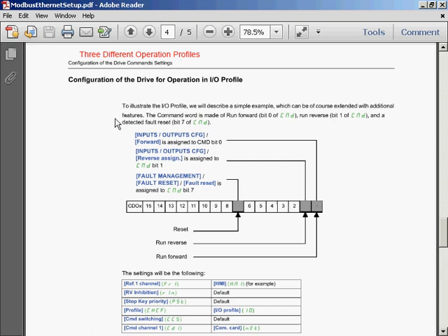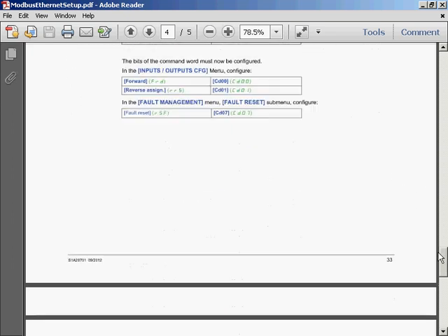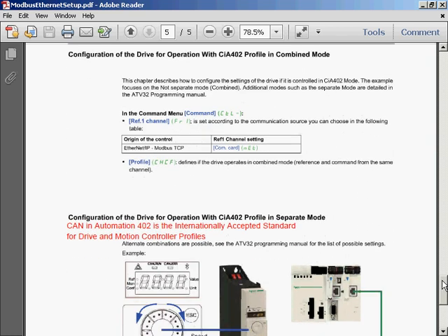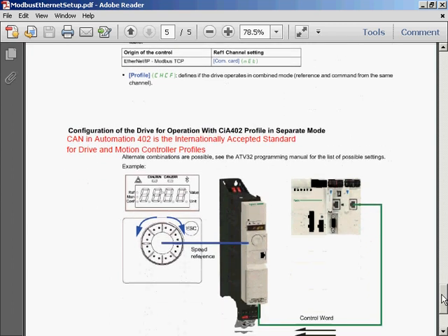The first is quite easy. See, it's just setting the drive up for I/O profile. That way, the communications that you use mimic the terminals that are on the drive itself. So, the other method of controlling the drive is using the CAN in Automation 402 standard. This is internationally accepted for drive and motion controller profiles. I'm going to use the separate mode.